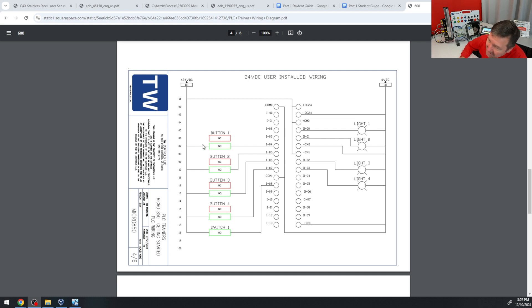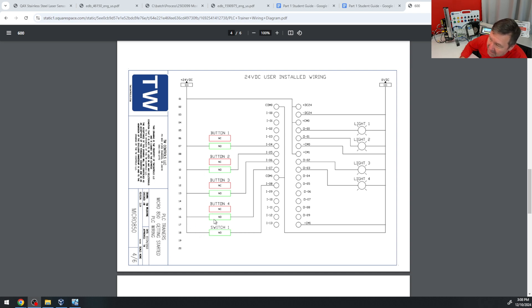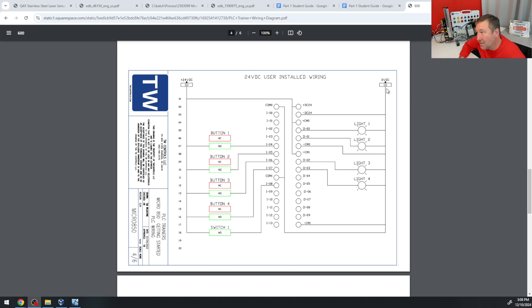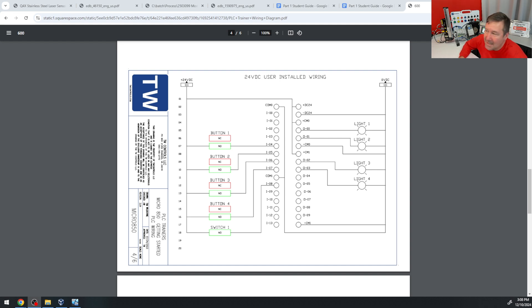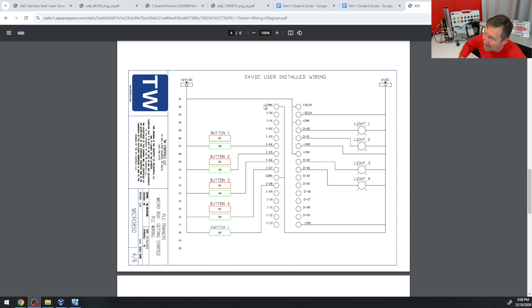And if we just look at this diagram here, then we see that this jumper is going across all the buttons. That means that, from the perspective of these buttons, our common is the plus 24 volt. Now, over here on the lights, we see the jumpers going across to the zero volt, or the minus. So that is the common of the lights. So our question next is, what is the definition of the COM0 on the Micro 850?